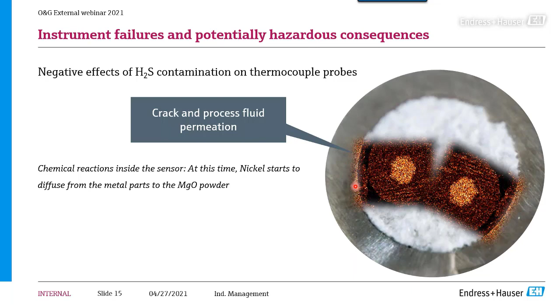The goal was to avoid formation of such sulfides happening again, or if it happens, that the thermocouple wires can feel it. So the idea was to protect each inner thermocouple, where my cursor is, with its own metal sheath. In this case, we see 1, 2, 3, and there is a fourth thermocouple, and each of them has its own hot junction.